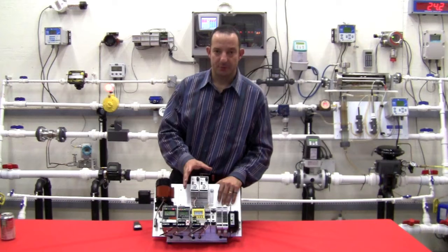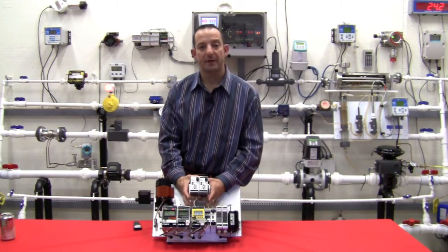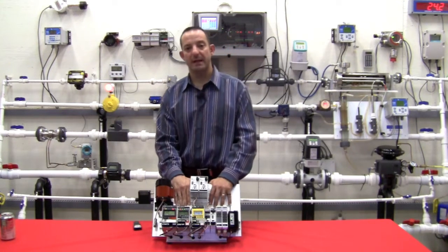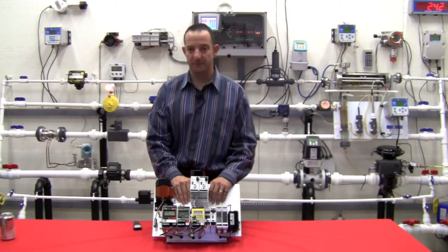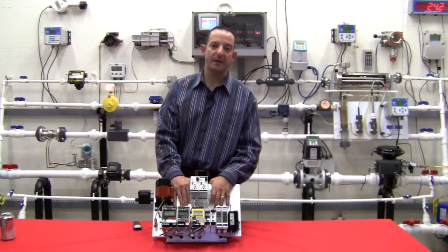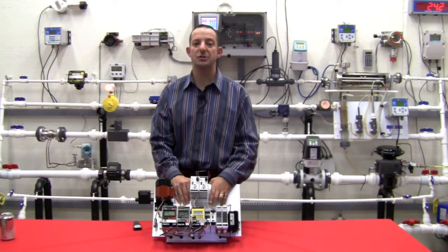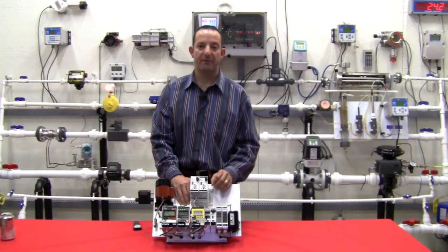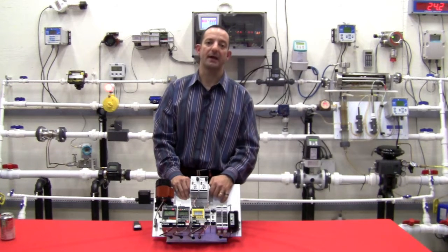For field mount units, which we don't have here in the demo case, we have units, like we said, that are available for hazardous area installation, and in particular for customers in the natural gas industry who often use natural gas to drive their valve actuators instead of compressed air. Our IPX2 I2P converter is available with a special NG option, which allows the unit to retain its FM approval for hazardous locations even when used with natural gas as the supply gas.